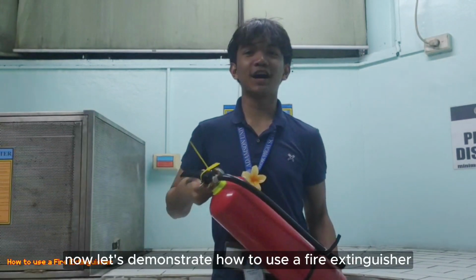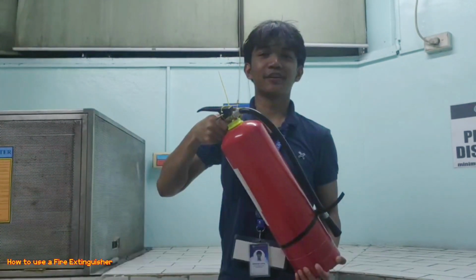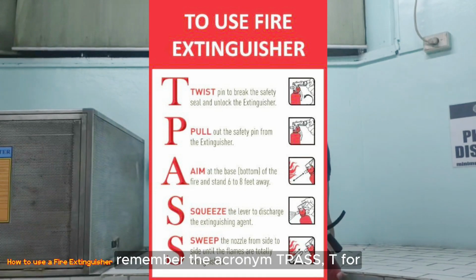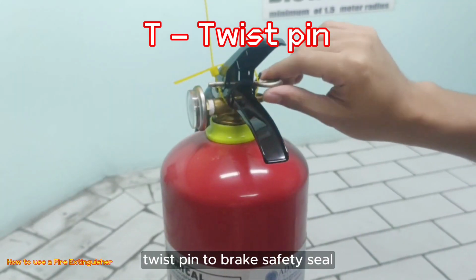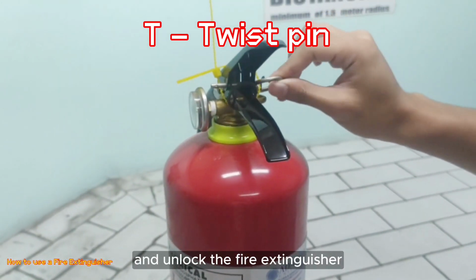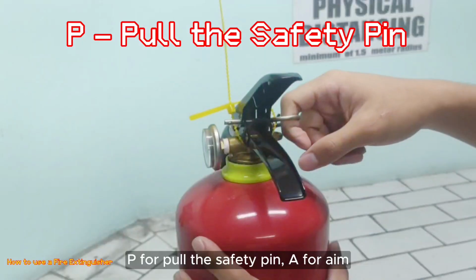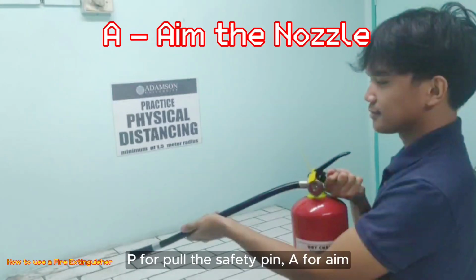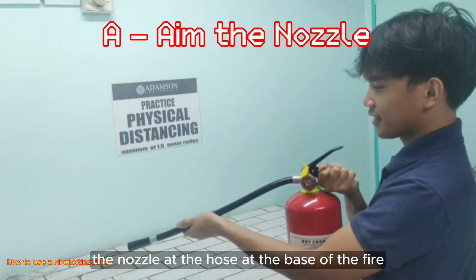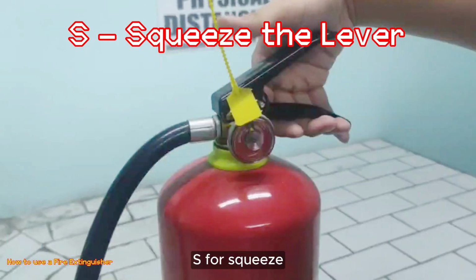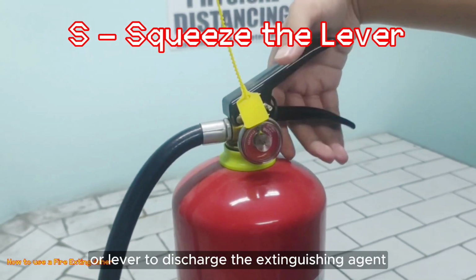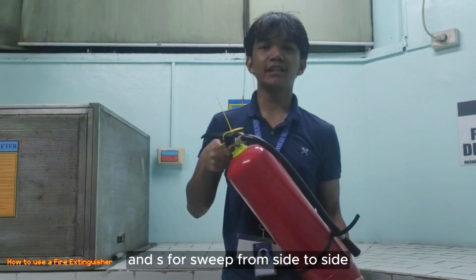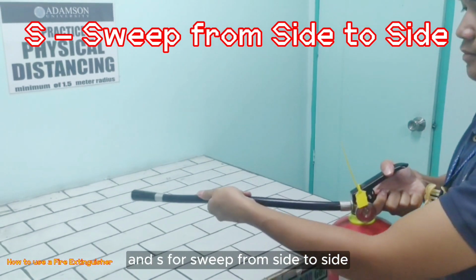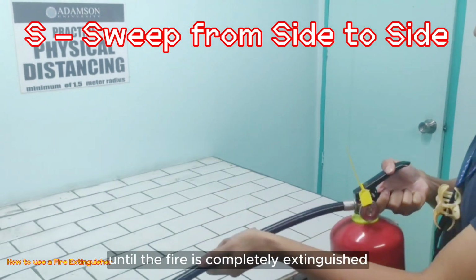Now let's demonstrate how to use a fire extinguisher. Remember the acronym TPASS. T for twist pin to break safety seal and unlock the fire extinguisher. P for pull the safety pin. A for aim the nozzle at the base of the fire. S for squeeze the handle or lever to discharge the extinguishing agent. And S for sweep from side to side until the fire is completely extinguished.